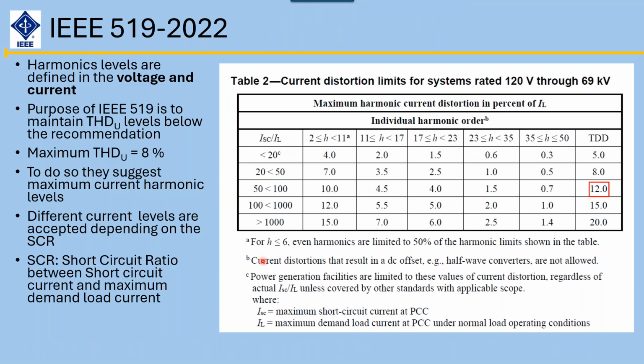Now let's talk about current. The way we determine the currents is we're going to look at the short circuit over the full load current. Basically, this is going to tell me how stiff my system is. If I have a very stiff system, the voltage isn't going to drop as much. If I've got a very weak district system, that voltage could fluctuate greatly with the current. So in the example I'm going to show in the next slide, we're going to end up in this 50 to 100, and we're going to end up with a TDD of 12. But I'll show you that in the next slide when I do it.